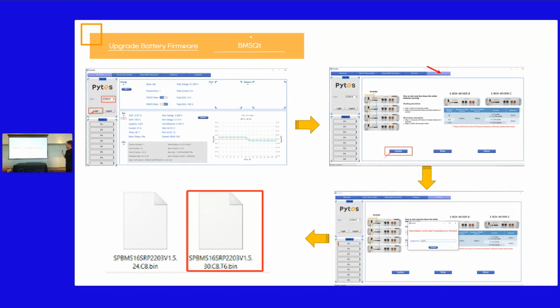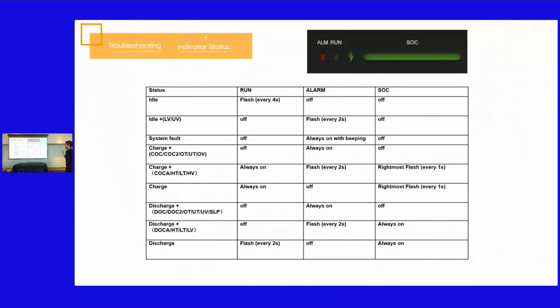The next part is troubleshooting. Here is the indicator state list. Alarm lights on the battery don't necessarily mean there's a problem. For example, if the alarm light just flashes, it could mean the battery is at high temperature, high voltage, low temperature, or low voltage. If the alarm light is always on, it could mean the battery is over temperature, over voltage, or under temperature, and has entered a protection state. You just need to restore the battery to normal operating conditions for the alarm to release.